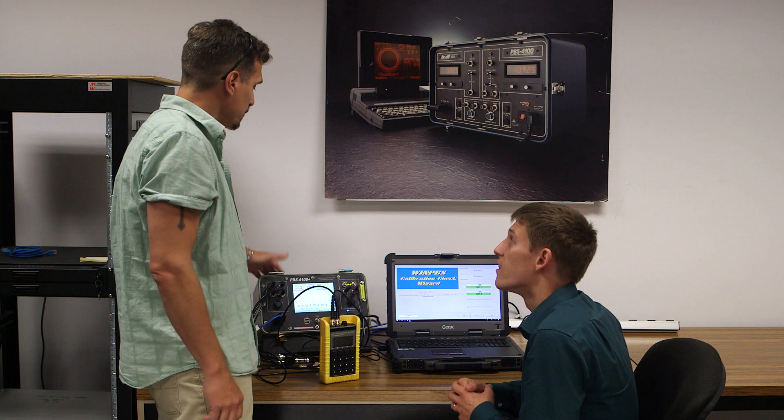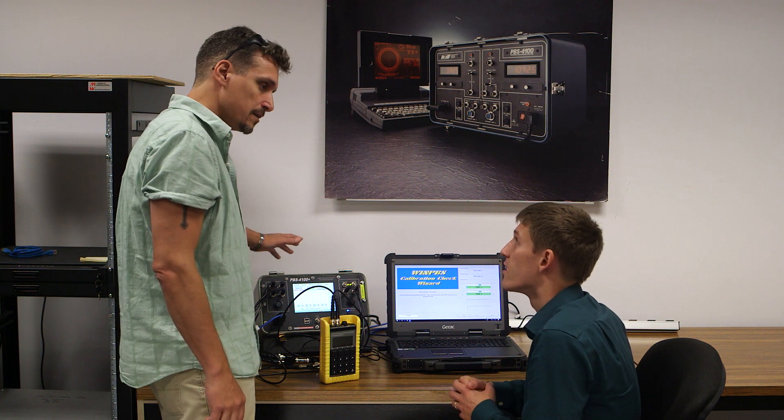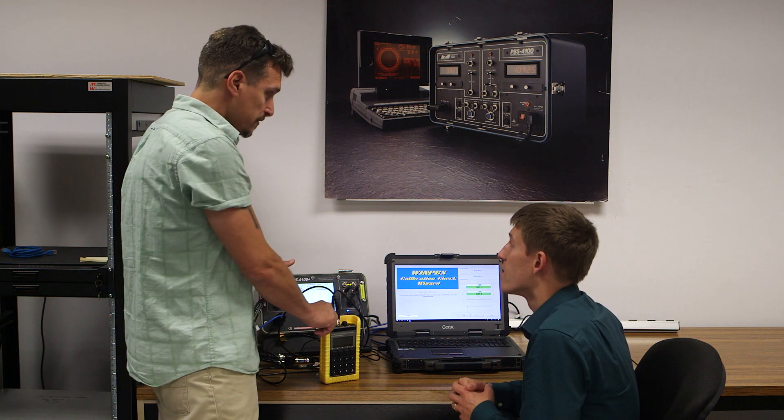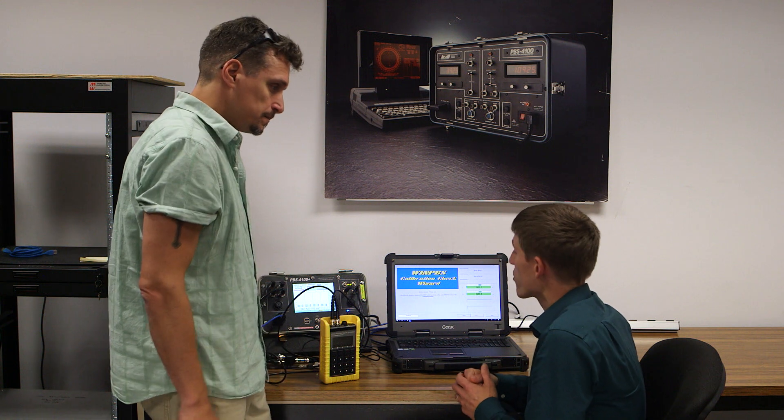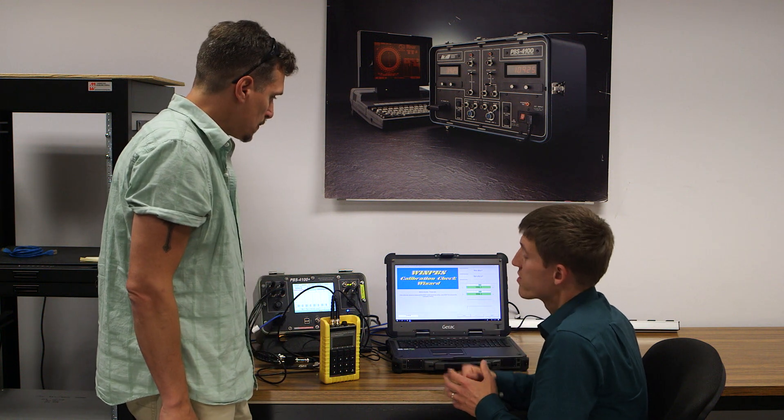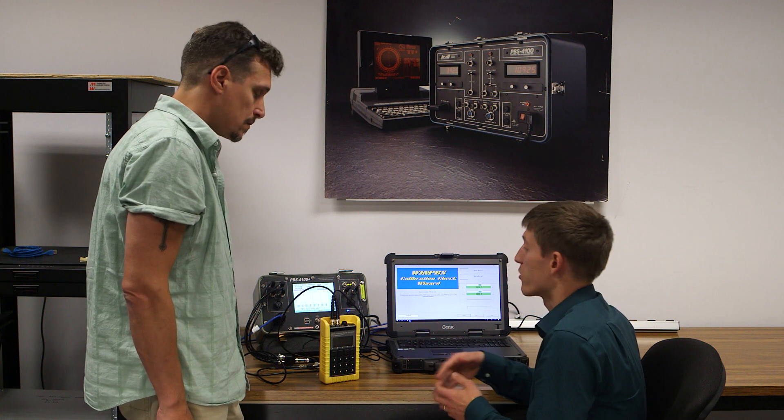Can you explain to me how difficult it may be to do a calibration check on the PBS4100 with the 1510? In order to test the calibration of a piece of equipment like this, you generally have to simulate a number of different frequency inputs and a number of different amplitude inputs to make sure that they're all functioning within tolerances.